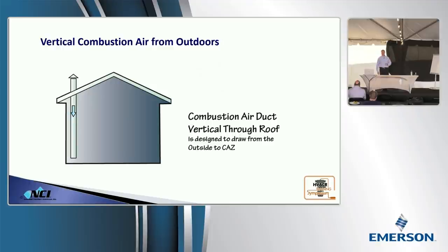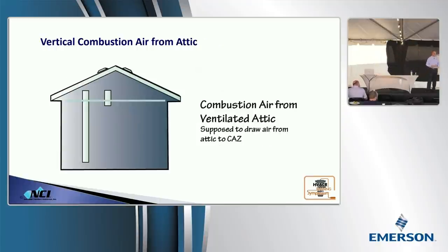Now what's the flue and what's the combustion air duct? Because air takes the path of least resistance. We can fix that. Here's a common one. This is probably the most common. Two pipes. One should be within how far from the floor? 12 inches. How far should one be from the ceiling? 12 inches. Why? No one knows. So, as we start to measure these, remember the top one's a secondary flue, the bottom one is supposed to be the inlet.